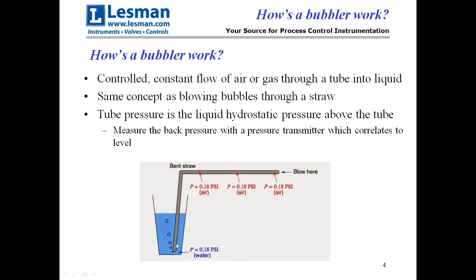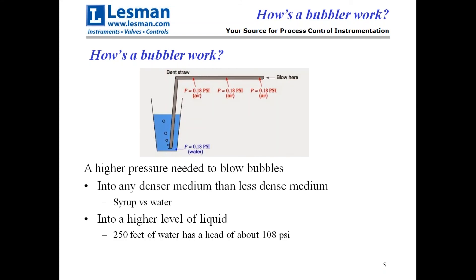In an industrial situation, we just measure the back pressure in the tube to determine what the hydrostatic pressure of the liquid column is. You need a higher pressure to blow bubbles into a denser medium than a less dense one. So for the same level, you have to have more pressure to push a bubble through syrup than through water. A 250-foot column of water has a pressure of over 100 psi.